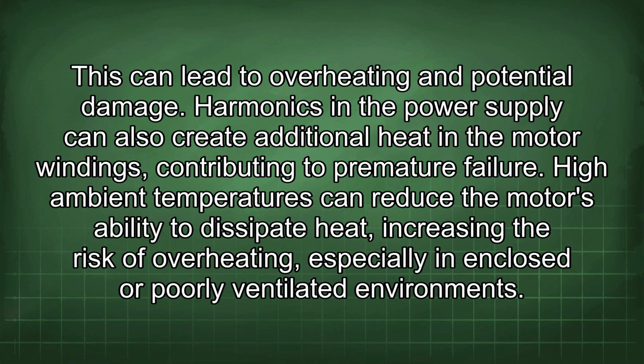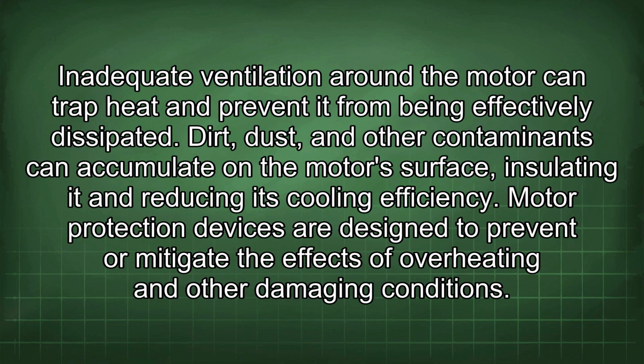High ambient temperatures can reduce the motor's ability to dissipate heat, increasing the risk of overheating, especially in enclosed or poorly ventilated environments. Inadequate ventilation around the motor can trap heat and prevent it from being effectively dissipated. Dirt, dust, and other contaminants can accumulate on the motor's surface, insulating it and reducing its cooling efficiency.